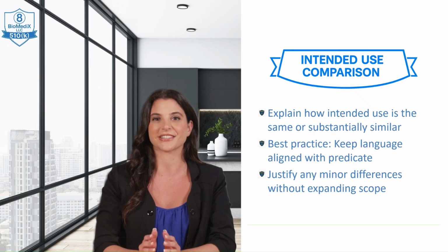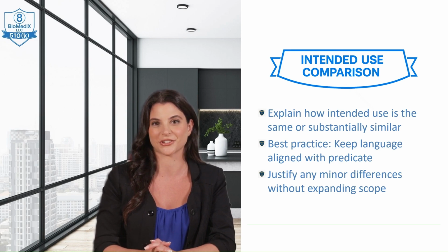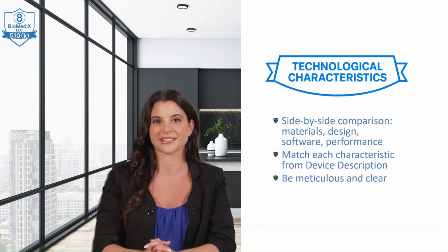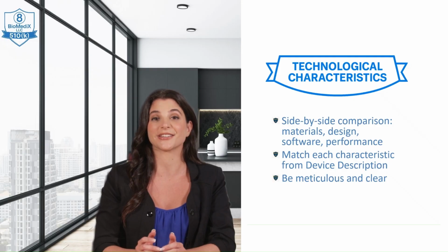The best practice is that if there are minor differences, you clearly articulate why these do not affect safety or effectiveness or raise new questions. Avoid expanding your intended use beyond that of the predicate without full justifications and supporting data.